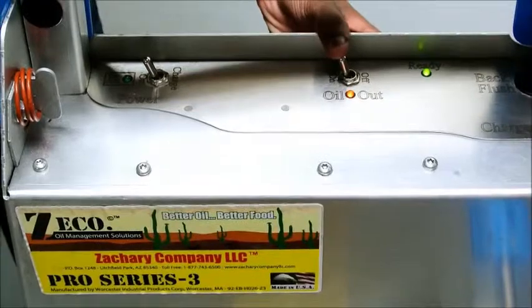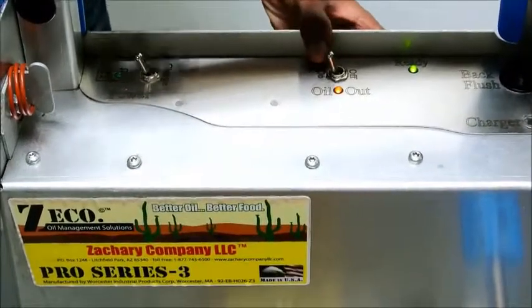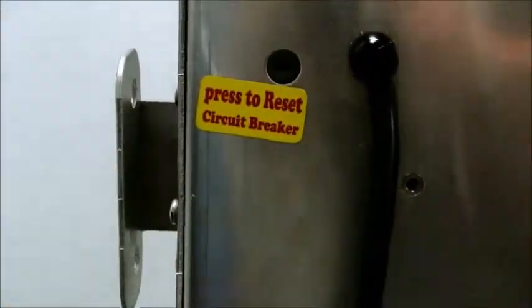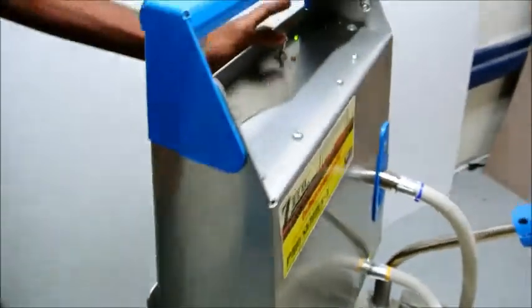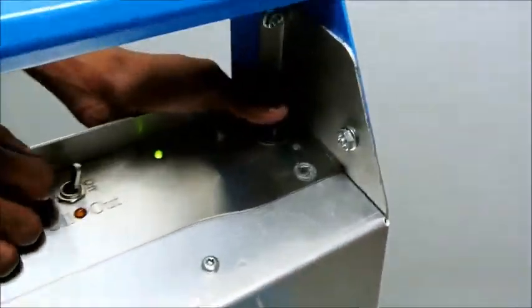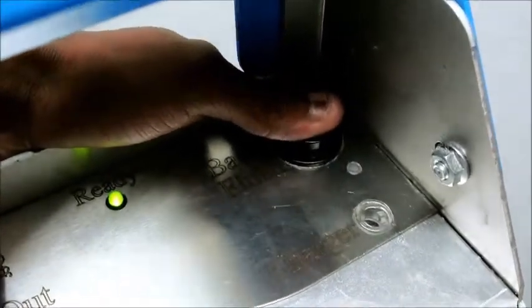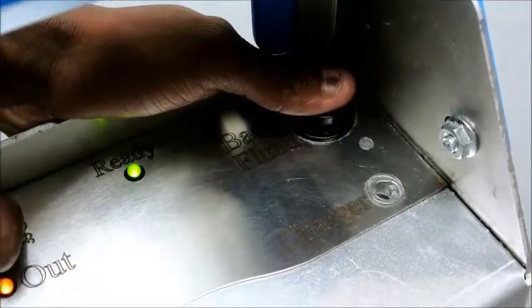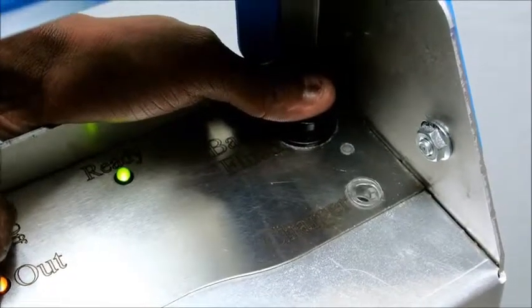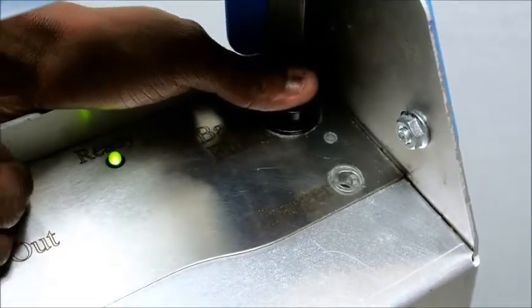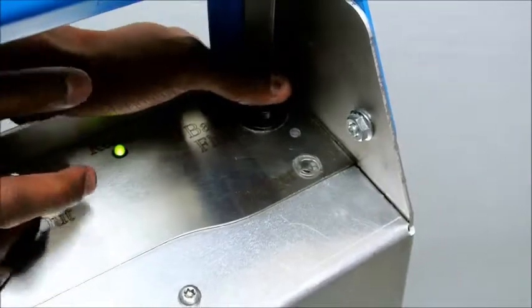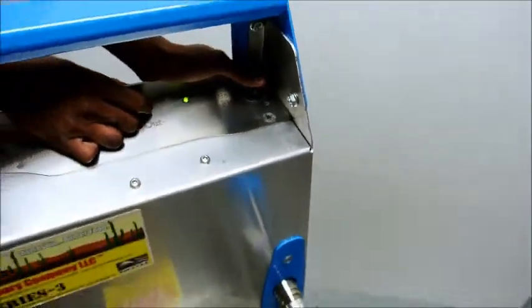If it pops again, you can hit the oil out switch to off, come down to the circuit breaker and depress it, then come back up to the switches, holding the back flush button. If the circuit breaker pops again, then we know it's a clogged pump, and I will show you how to fix that.